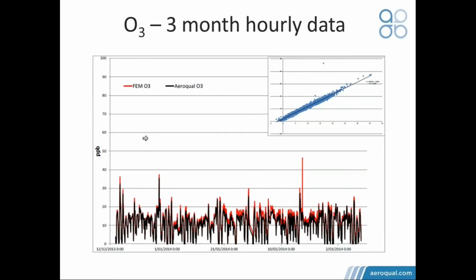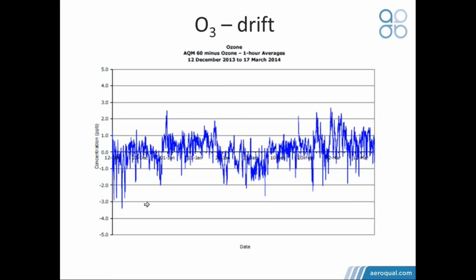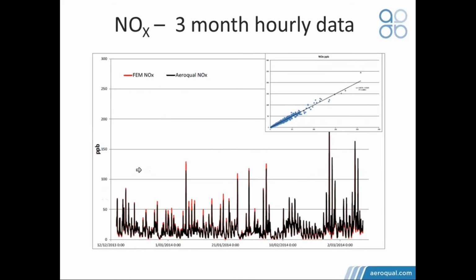There were no calibrations of the Aeroqual ozone. We just wanted to let it run. Here is the drift over that time. So this is the hourly ozone 1 hour average difference between the AQM60 and the reference station, and this is ppb levels here over a 3-month period, and you can see that there was no noticeable drift, but there were variances of a few ppb. So the instrument is very stable. Equally, this is the NOx data over that 3-month period, and again a very good correlation with the reference site data.